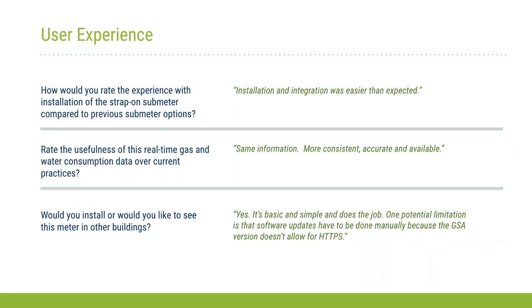Some of the usefulness of this data: it was the same information we had before, but it was more consistent, accurate, and available. And it's easy to adjust the K-factor. So if we ever needed an adjustment on a K-factor, or the utility came and replaced a meter, we know now that it's as easy as reinstalling that probe on the new meter, using the information that the vendor provided on the best locations for each meter. They have a catalog of meters that they've tested, and they found the best locations for the best quality of data that you could provide. So it made it really easy to install, and the information was really useful for us to use.